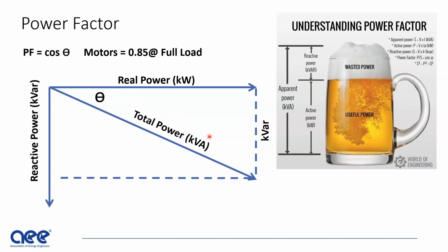But I did want to show you that this kVAR value here, it is necessary for the motor, but if you're lightly loaded, you can address this kVAR issue with two solutions. One is to use offsetting power factor correction capacitors, or use a VFD. A VFD will give you unity power factor at all loads.